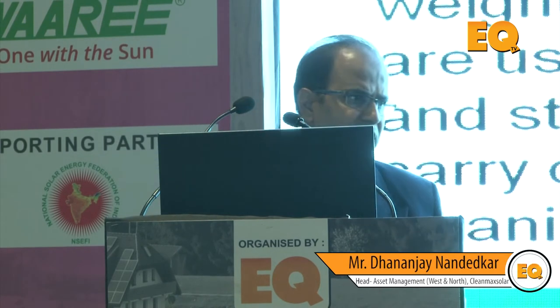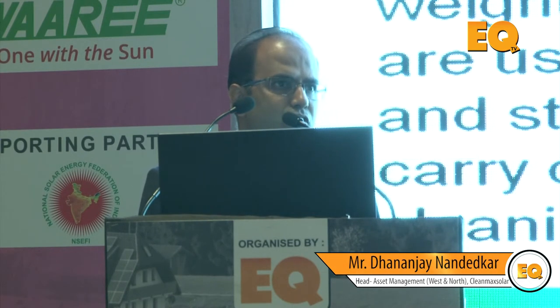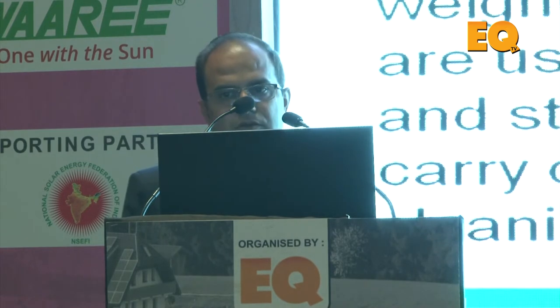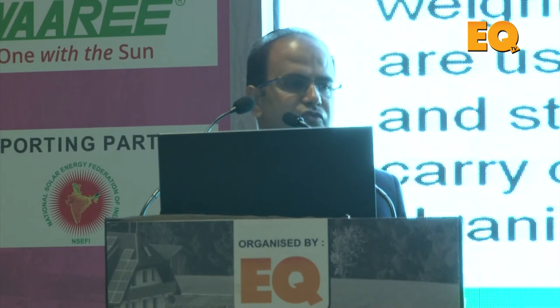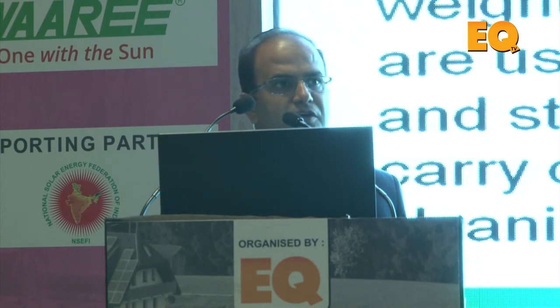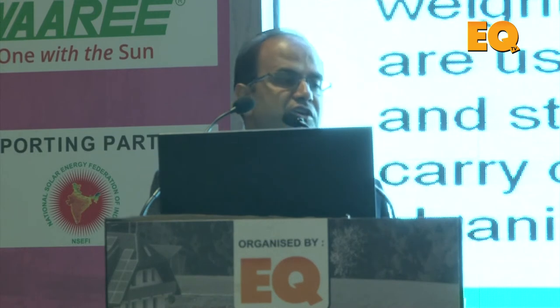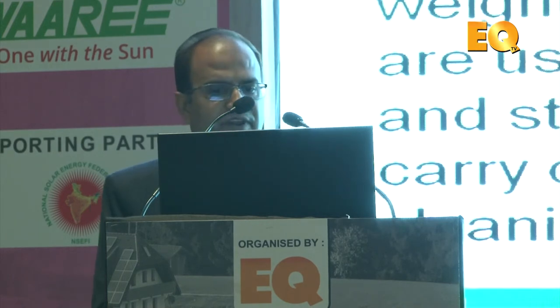When working at height — on carports or superstructures — safety ladders must have handrails and a standing platform so that cleaning activities can be carried out seamlessly. When there is no access to an industrial roof at heights of 12 to 15 meters, monkey ladders are used. Monkey ladders must include a landing platform so the person can hook their safety harness onto the lifeline. All ladders should have handrails.